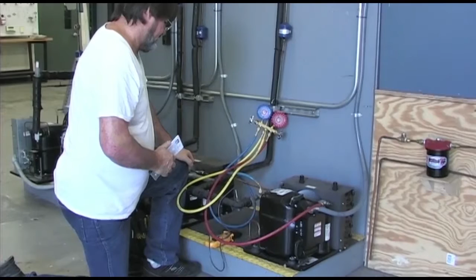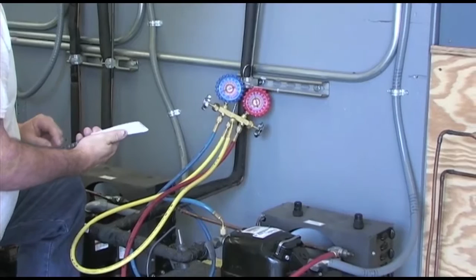What he will do now is take the low side pressure and use this PT chart to convert that pressure to a temperature. What's your temperature? Minus 10 degrees Fahrenheit saturation. Now we will look at our thermometer to see what our suction line temperature is.